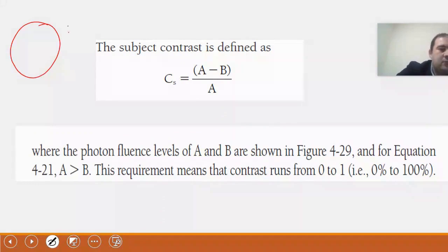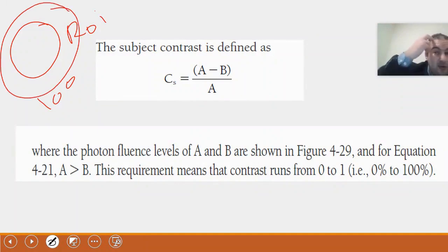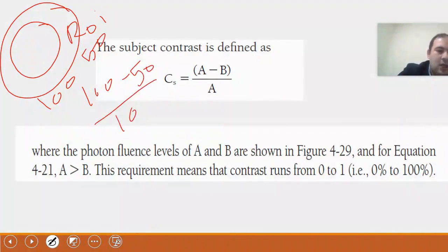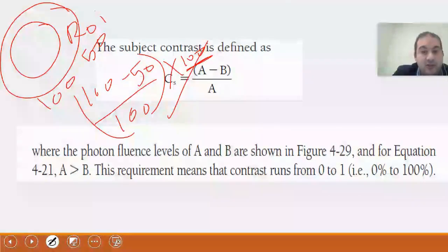Taking the ROI, region of interest, for example, my median CT number is 100. Then I look at the surrounding background attenuation, which is, for example, 50. So it would be 100 minus 50 over 100. Multiply it by 100 if you want it as a percent, which gives you the contrast value or the contrast of the image. This serves as a quantitative assessment for you.